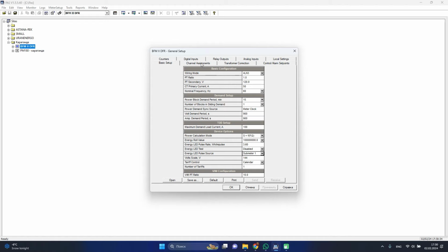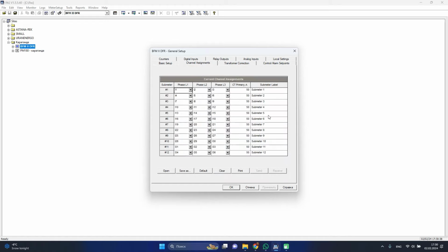In the BFM II DFR we have about 12 submeters, and for every submeter we can change the phases for our connections, the CT primary, and also we can change the submeter label. For example, feeder number 34, and for example kitchen, we can write it in the submeter label. We can change the CT primary for this one, for example to 200. And after that we need to send these setups to the device.